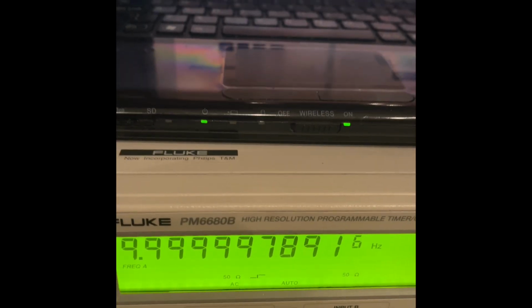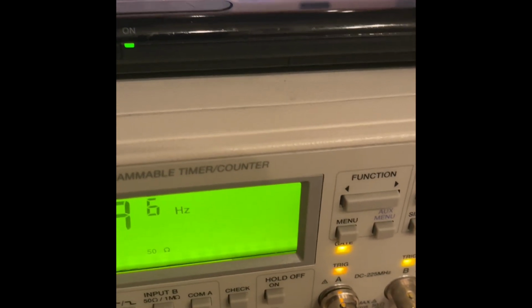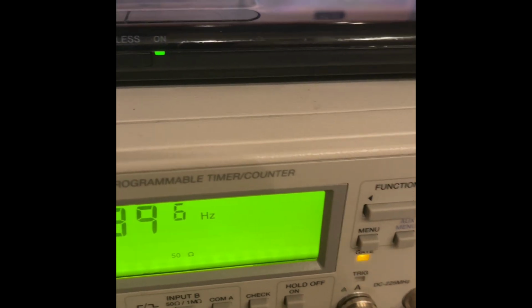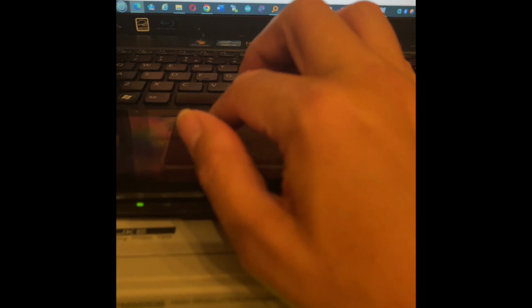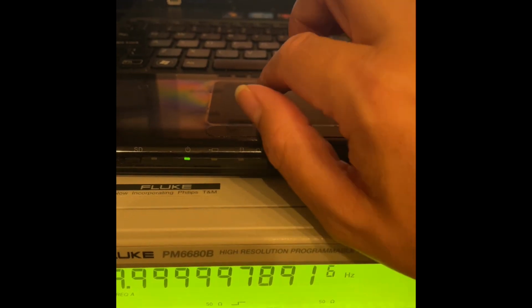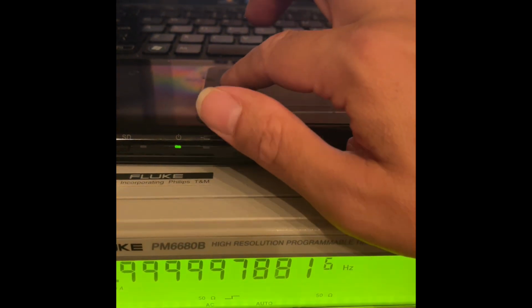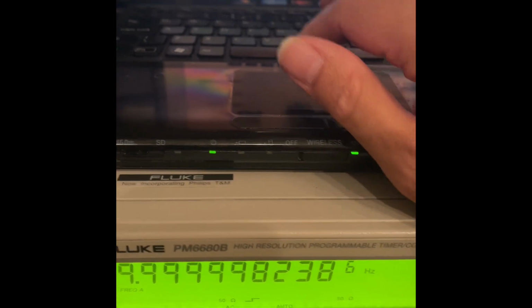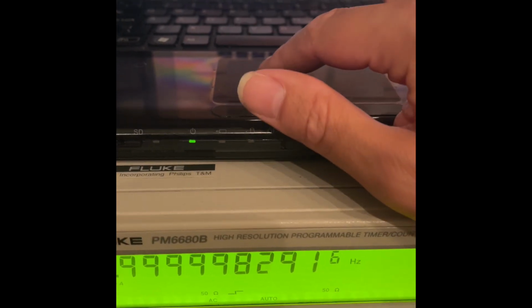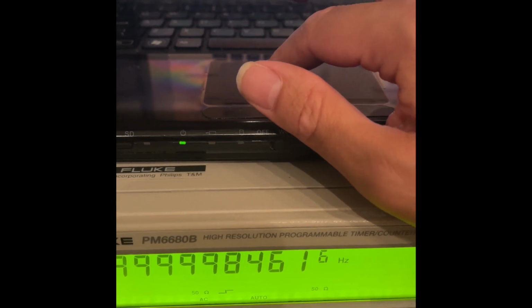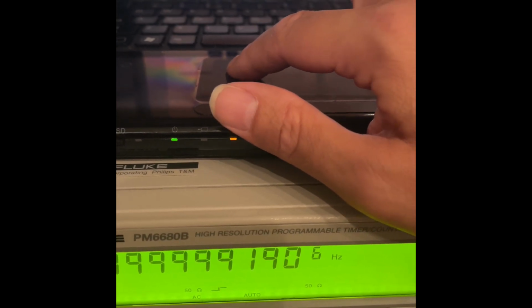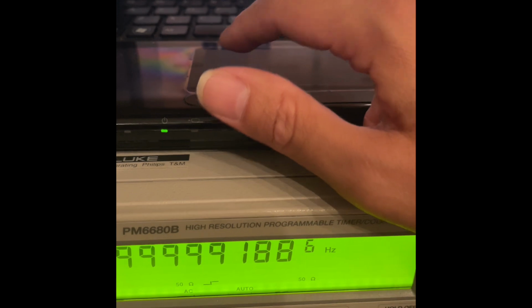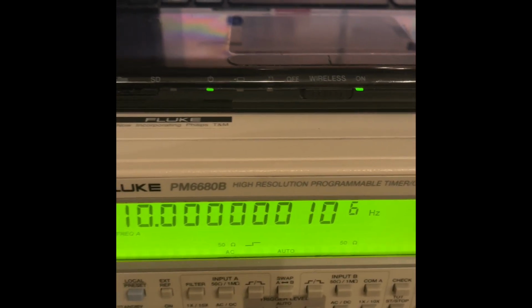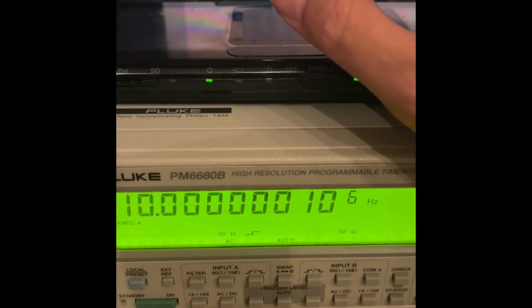As we can see, the calibration frequency is well off. We've got the GPSDO coming in here. That's a really steady 10 megahertz signal. And then we're going to go up to here. We're going to move the mouse over to the trim. I'm going to watch the frequency change as we trim the frequency. So here we go. Bring it down. Whoops. Laptop's moving on me. Let's bring it down to about 400 millivolts. 407 millivolts. There you go. It's nearly on there. So you can see the frequency's changed. Now we need a little trimming there.